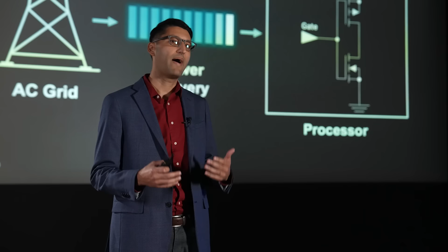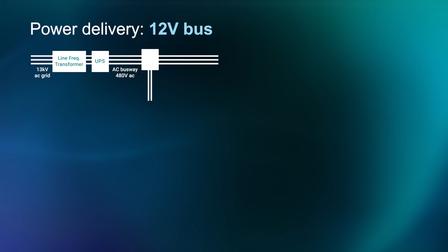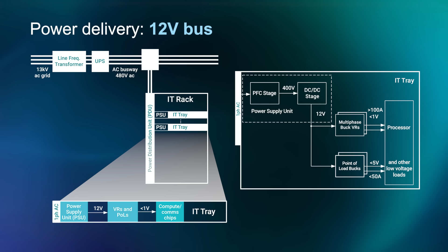You'd have a line frequency transformer converting power from the AC grid, which might be taking tens of kilovolts in, and converting that down to some lower voltage level, maybe 480 volts AC, that's distributed within the data center. There might be an uninterruptible power source at the facility level that provides backup power in the case of grid failure. Next, you'd have some power distribution unit that routes power to each tray in the IT rack. The tray itself would include a power supply unit, or PSU, that typically would have a single-phase AC input, and you might actually have two power supplies used for redundancy.